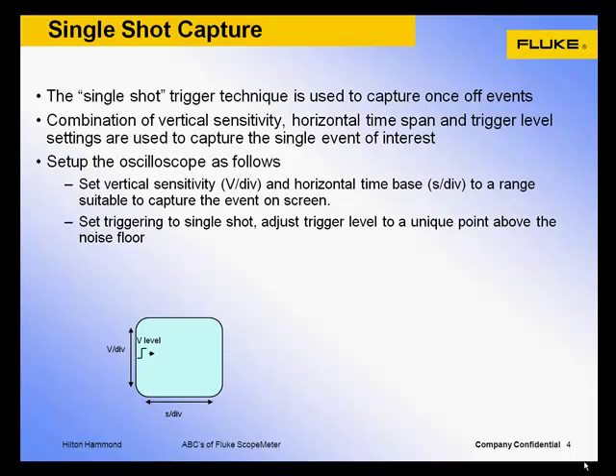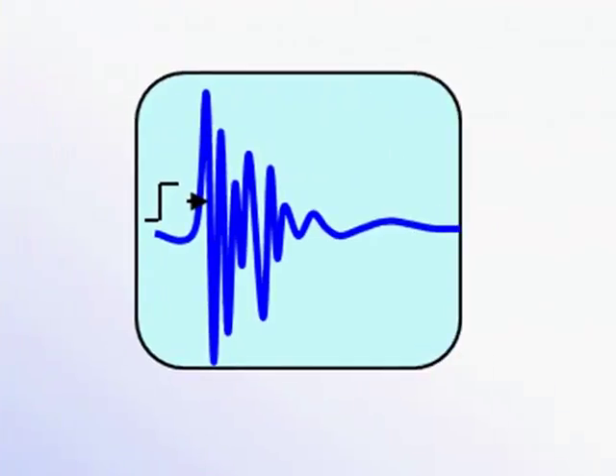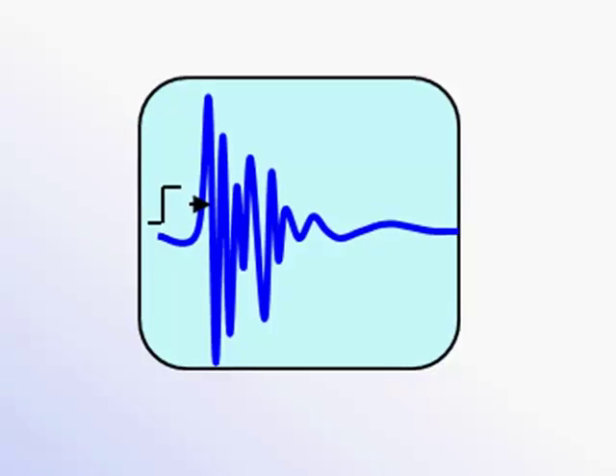Set up the oscilloscope as follows. First, set the vertical sensitivity, making sure that the expected amplitude of the waveform will be within the vertical range of the scope. Set the horizontal time base to capture the desired time span of the unknown waveform. Next, set the trigger mode to single shot capture. Then adjust the trigger level to just beyond the signal noise floor or at 50% of the expected waveform amplitude. The scope is now armed, waiting for the next occurrence of the event. Once captured, the scope will freeze until the trigger display update is manually re-armed.